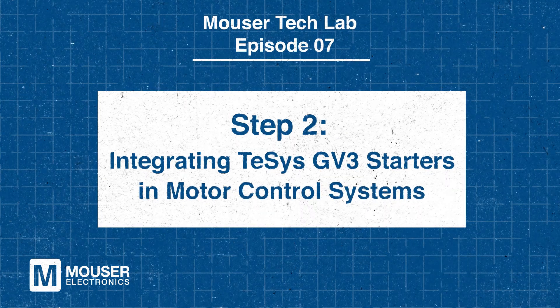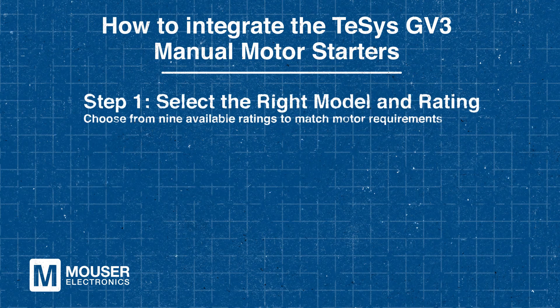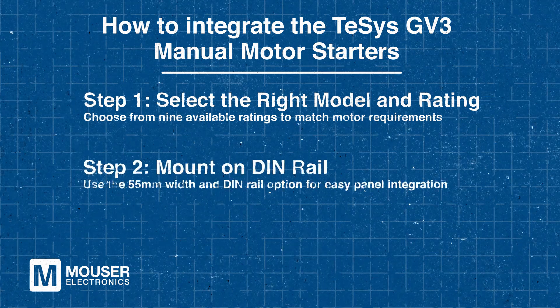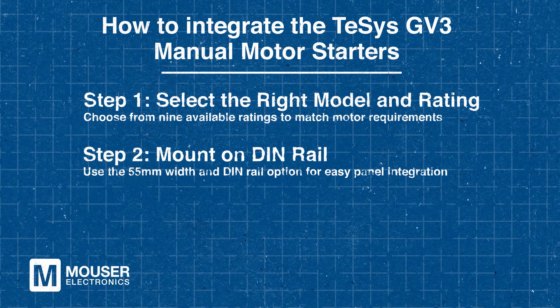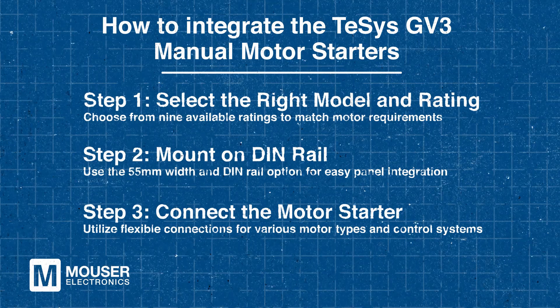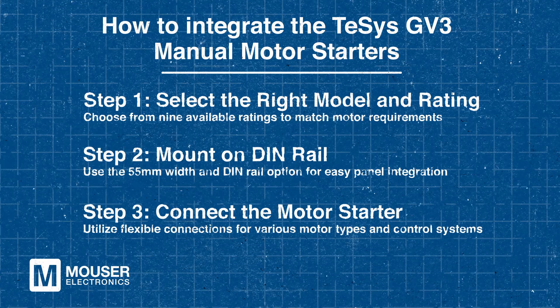Step 2: Integrating TeSys GV3 Starters in Motor Control Systems. Now that we know a bit more about the TeSys GV3, let's discuss how to effectively integrate them. Begin by selecting the right model and rating — the GV3 Series offers 9 ratings to match different motor sizes and requirements. Next, mount the 55mm standard width unit on a DIN rail to simplify integration into existing control panels. Then connect the motor starter using its flexible connection feature, which allows easy adaptation to various motor types for simple or complex control systems.